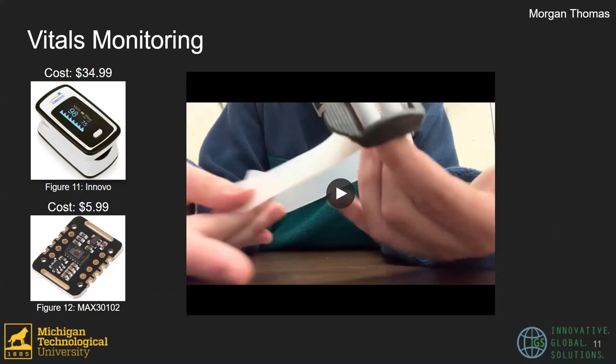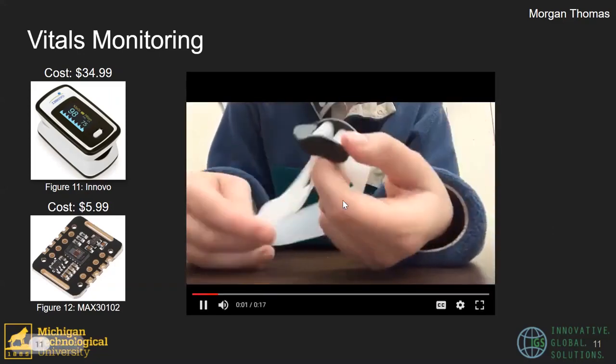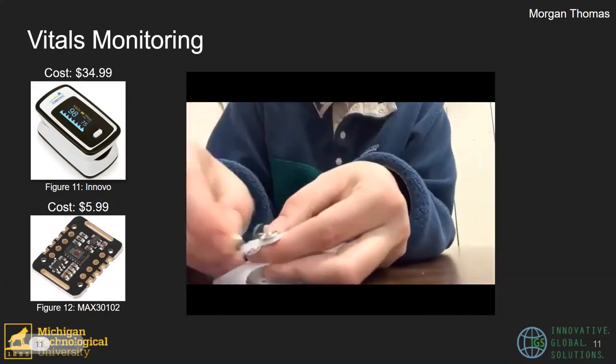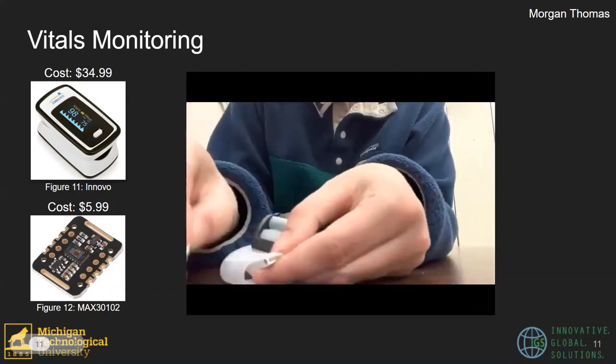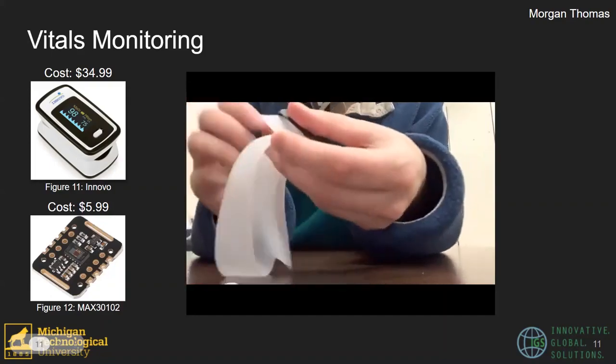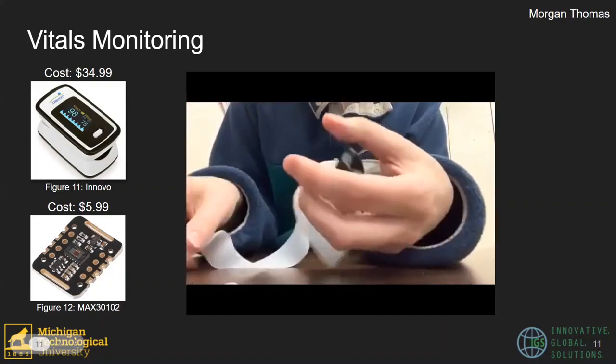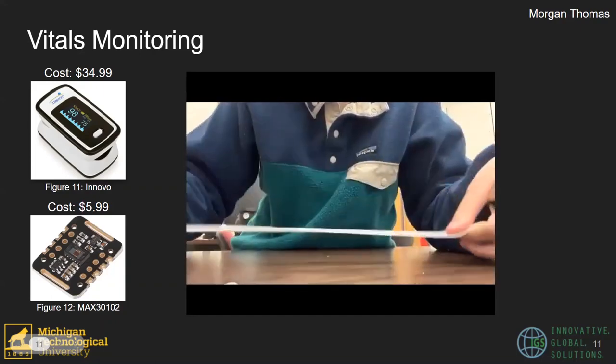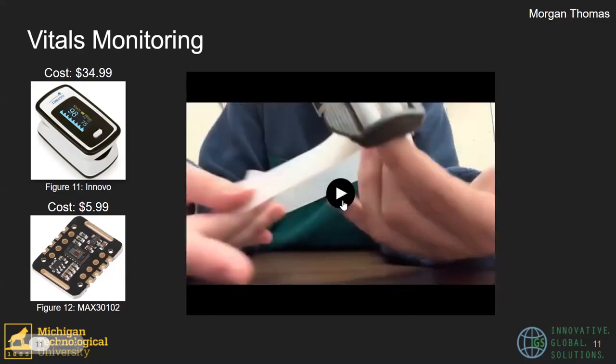To help drive costs down, we used a reusable silicone band, implemented along with the sliding buckle and snap buttons. These components can easily be taken apart for easy sterilization and will have minimal irritation to the infant due to silicone's chemically inert properties and ability to lay naturally flat to the infant's skin, reducing any unnecessary tightness of the band around the foot.